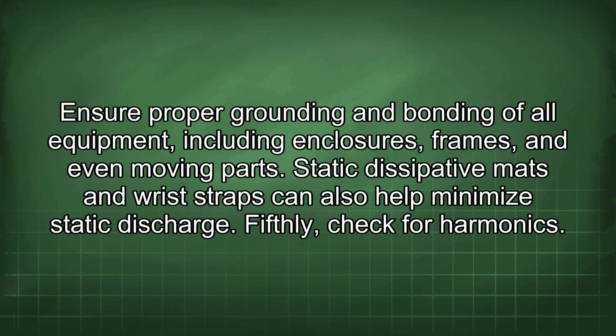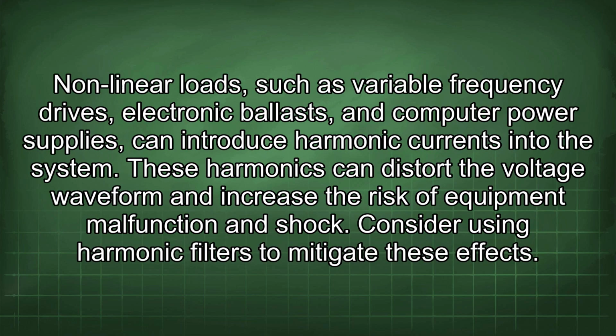Fifthly, check for harmonics. Nonlinear loads such as variable frequency drives, electronic ballasts, and computer power supplies can introduce harmonic currents into the system. These harmonics can distort the voltage waveform and increase the risk of equipment malfunction and shock. Consider using harmonic filters to mitigate these effects.